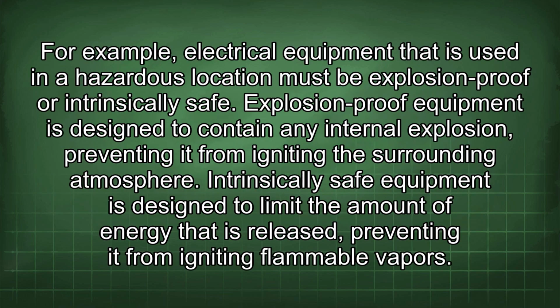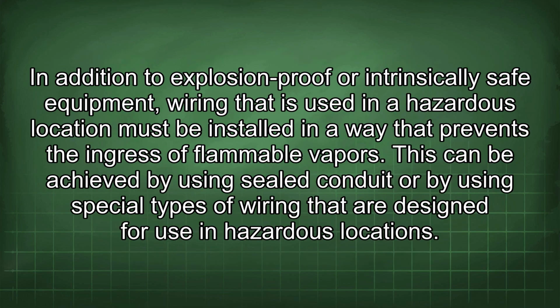For example, electrical equipment that is used in a hazardous location must be explosion-proof or intrinsically safe. Explosion-proof equipment is designed to contain any internal explosion, preventing it from igniting the surrounding atmosphere. Intrinsically safe equipment is designed to limit the amount of energy that is released, preventing it from igniting flammable vapors. In addition to explosion-proof or intrinsically safe equipment, wiring that is used in a hazardous location must be installed in a way that prevents the ingress of flammable vapors.